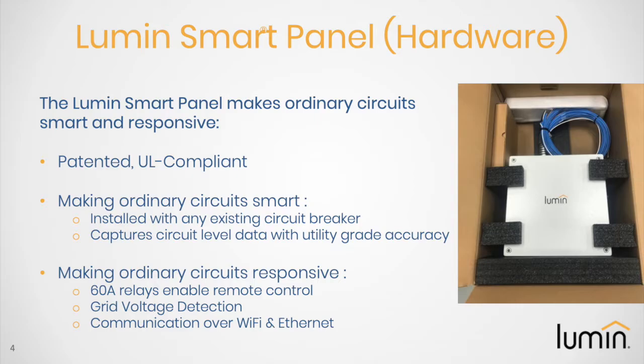On the hardware side, Lumin sits between the existing electrical panel and your loads. It installs in about 4 hours and can switch and control up to a 60 amp load. From an installation standpoint, we intercept the load wire: you remove it, insert the Lumin wire into the box, and current flows through our Lumin box, where we have electromechanical relays. The second Lumin wire comes out and gets wire-nutted to the load wire.